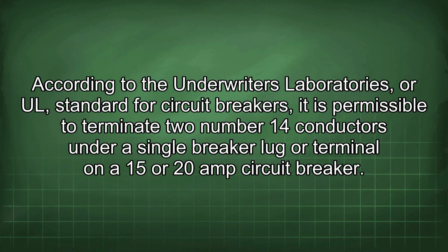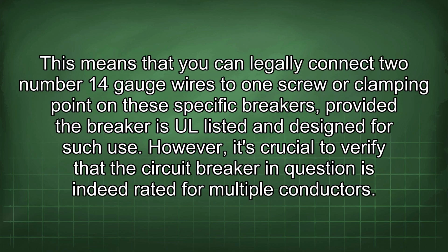According to the Underwriters Laboratories, or UL, standard for circuit breakers, it is permissible to terminate two number 14 conductors under a single breaker lug or terminal on a 15 or 20 amp circuit breaker. This means that you can legally connect two number 14 gauge wires to one screw or clamping point on these specific breakers, provided the breaker is UL listed and designed for such use.